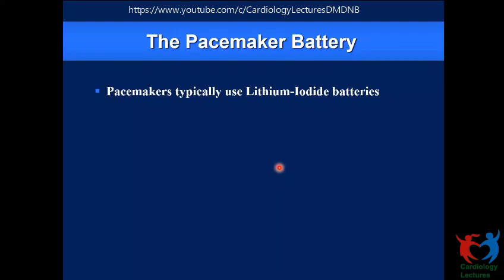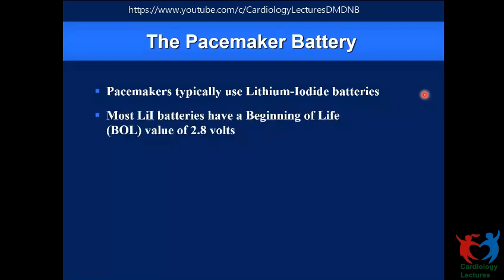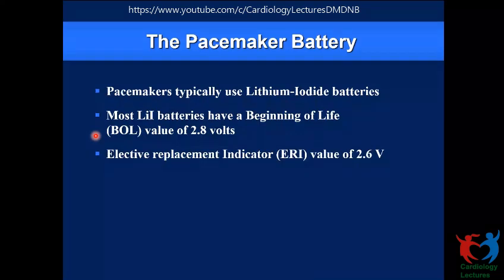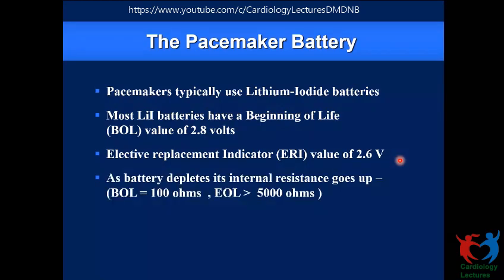The most recent pacemaker batteries are slightly different. The conventional batteries are lithium iodine batteries. So these lithium iodine chemistry based pacemakers will provide a voltage of 2.8 volts, no matter how big or small the battery is, the output that will come from that cell will be 2.8 volts, which is also called the beginning of life voltage, and the current annotation is actually beginning of service, called BOS. And then gradually, after connecting to the lead inside the patient's heart, it lasts for some amount of time, and then it reaches a certain voltage, at which point we declare the elective replacement indication, which is also referred to as ERI. Sometime even further below that, it is said to have reached the EOL, or end of life, or end of service.